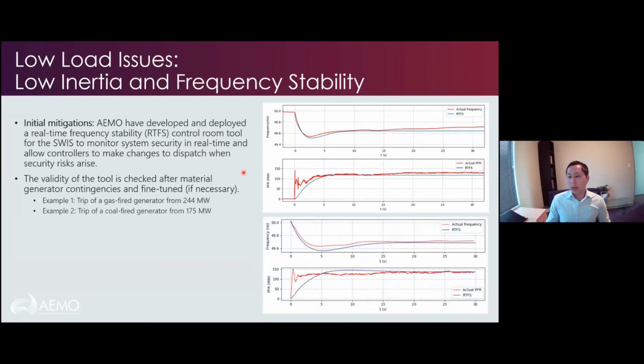Another example is a coal-fired generator at 175 megawatts, and again, RTFS is fairly accurate in the sense that we're within 0.1, 0.2 hertz at the nadir, and it's conservative, which so far is so good.